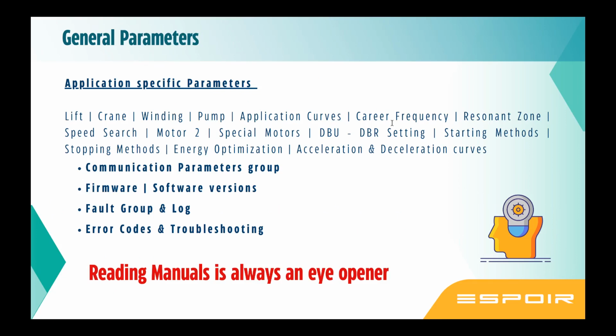So you have to select a proper starting method and stopping method. There are different starting and stopping methods, like coast to stop, which means you are allowing the motor to stop on its own. It will take a lot of inertia to stop. So if your application demands an immediate stop, you need to use deceleration to stop, which is a standard feature used.